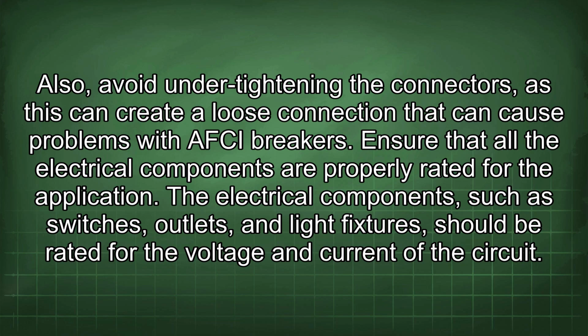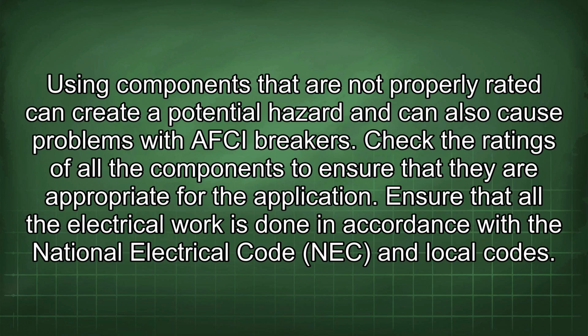Ensure that all the electrical components are properly rated for the application. The electrical components, such as switches, outlets, and light fixtures, should be rated for the voltage and current of the circuit. Using components that are not properly rated can create a potential hazard and can also cause problems with AFCI breakers. Check the ratings of all the components to ensure that they are appropriate for the application.